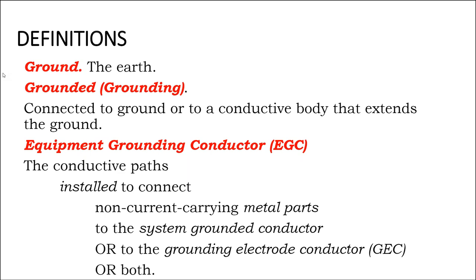Well, if you don't, then that voltage that doesn't spark, but it's still touching the sides of the metal, is bringing that metal box up to a high point of voltage. And then you go and touch it, all of a sudden you're the path to ground. You're the low voltage potential.